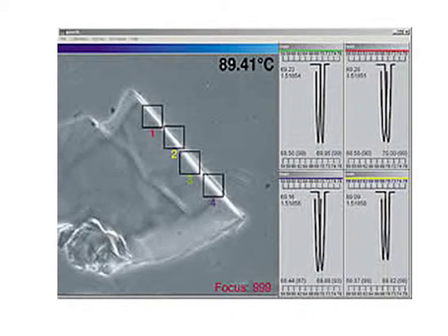Thus, it does not form a good discrimination between sources. The refractive index of the liquids can vary with the temperature of the liquid. So, the laboratory temperature is to be maintained at a fixed value, else error can be introduced in the system. Now, due to these limitations, automated glass refractive index measurement was introduced.